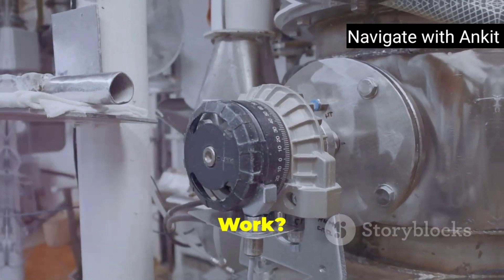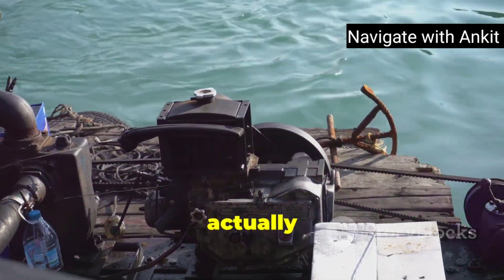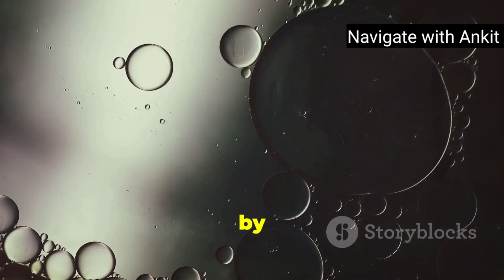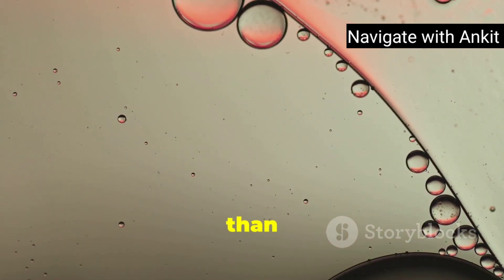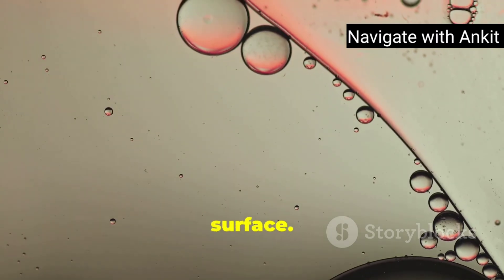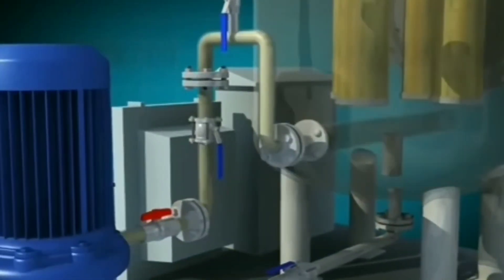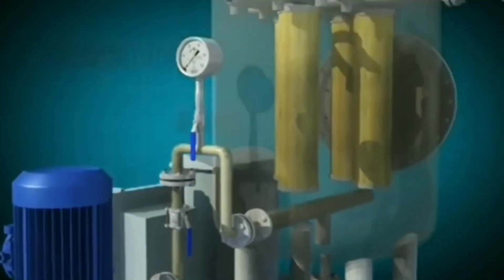Now let's talk about how this machine actually works. The principle behind an OWS is pretty simple — it's all about separation by gravity. Oil is less dense than water, so it naturally rises to the surface. Let's break down the process in stages. First, the initial stage: coarse separation.